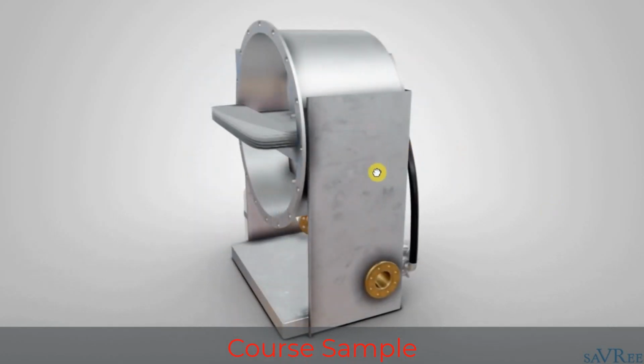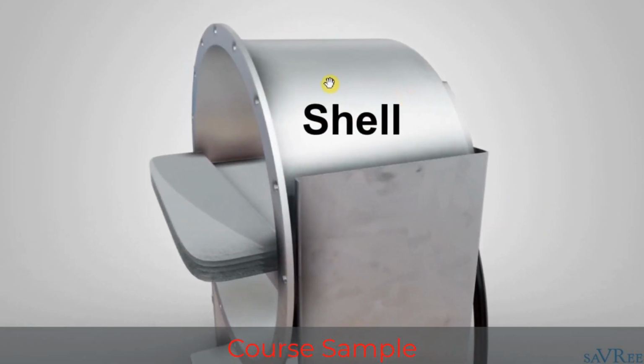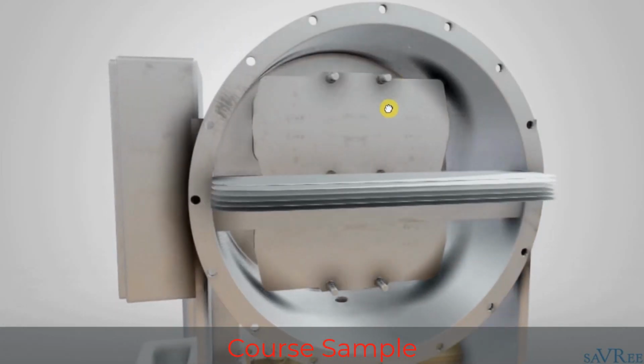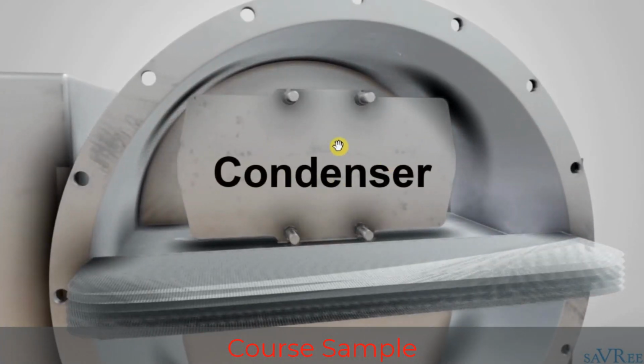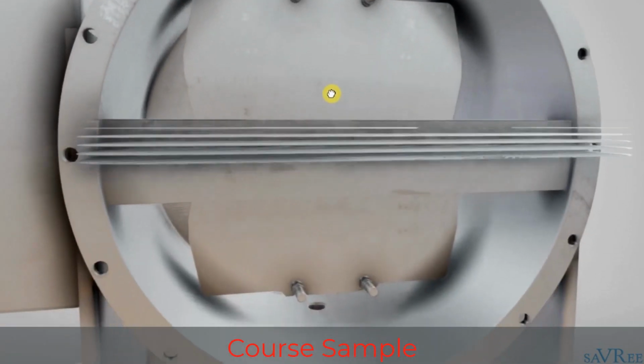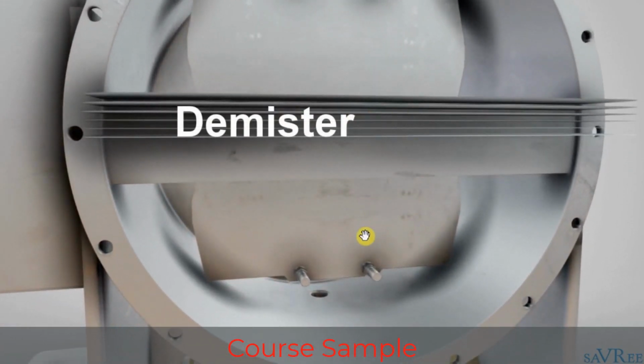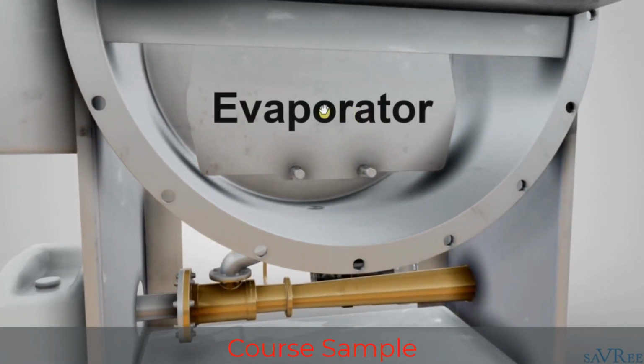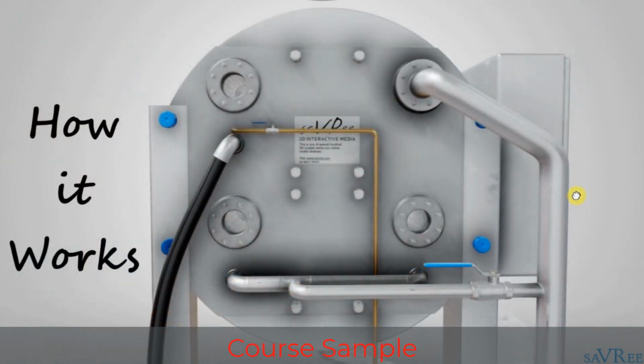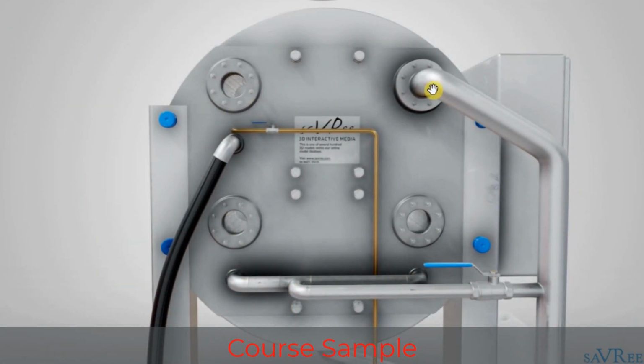The main metal body is referred to as the shell, that's this piece here. Within the shell we have a condenser, that's this piece, a demister in the middle, and an evaporator, that's this piece here. We've got seawater coming in here and seawater being discharged in the top right.